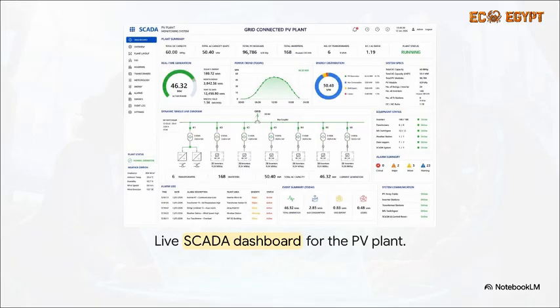And ultimately, all of this hard work, all the calculations, the grid studies, it all comes to life on the SCADA dashboard. That supervisory control and data acquisition system captures your active and reactive power, your voltage set points, curtailment commands, the whole shebang. It completely proves that these degradation factors and QV profiles are not just academic exercises. They translate directly into a living, breathing, continuously monitored 50-megawatt power plant operating dynamically right there with the grid.